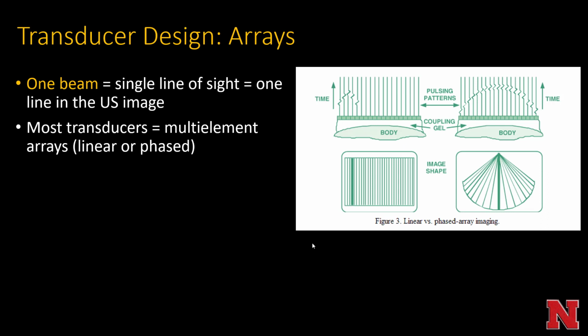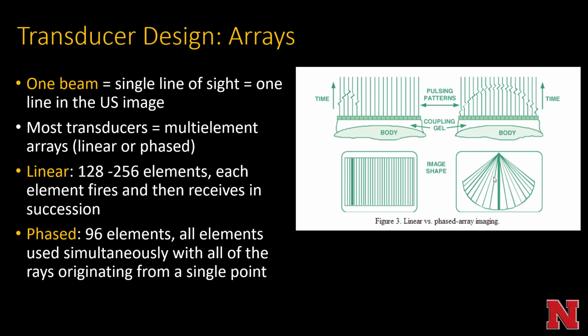Transducer design arrays: one beam is a single line of sight, one line in an ultrasound image. Most transducers are multi-element arrays, either linear or phased array, with different applications. Linear usually has 128 to 256 elements, each firing and then receiving signals in succession. A phased array transducer, like a transvaginal probe, might have 96 elements, all used simultaneously with all the rays originating from a single point.